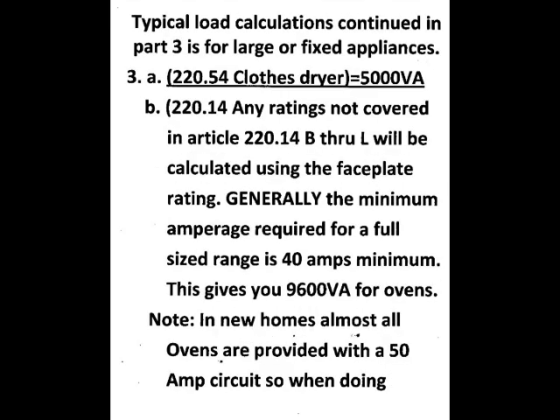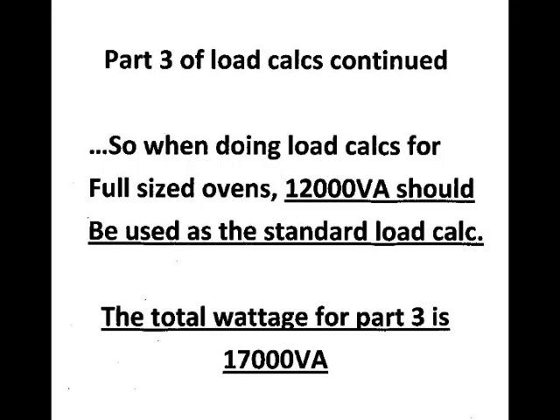Next, you'll probably have a section 3. Section 220-54 tells you that a clothes dryer is rated at 5,000 volt amps. Generally, the minimum amperage required for a full-sized range is 40 amps. However, in almost all new homes, ovens are provided with a 50 amp circuit. So when you're doing your load calcs for full-sized ovens, 12,000 volt amps should be used as the standard load calc. The total wattage for section 3 is 17,000 volt amps.